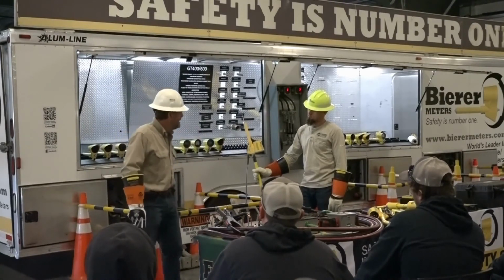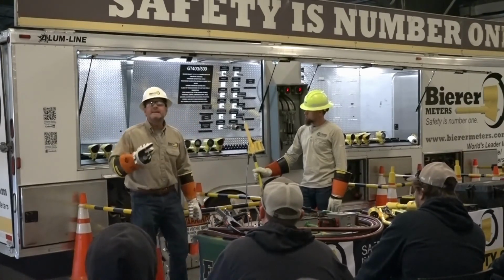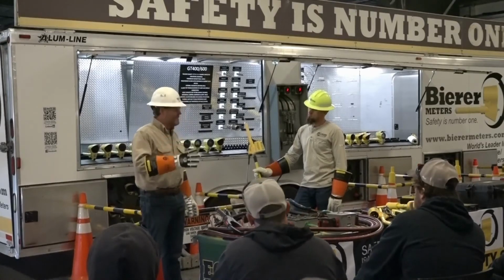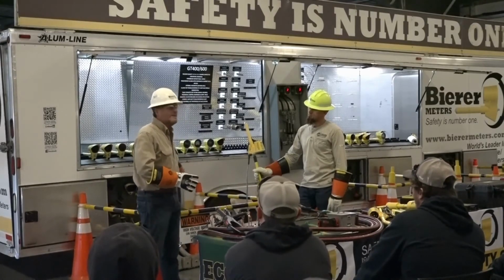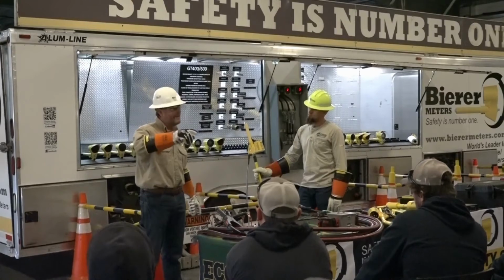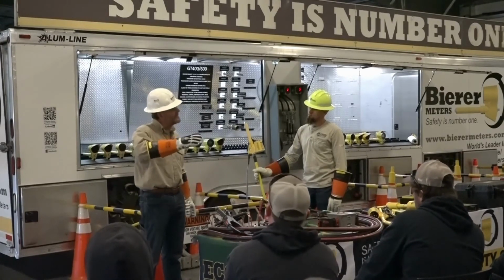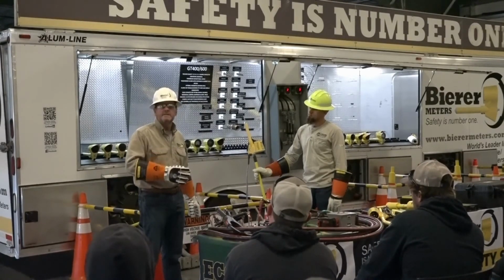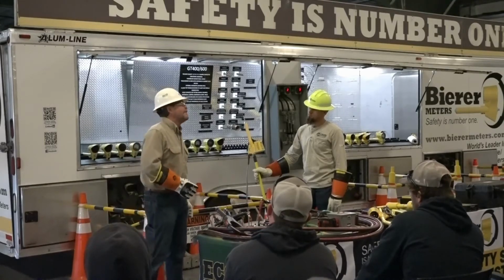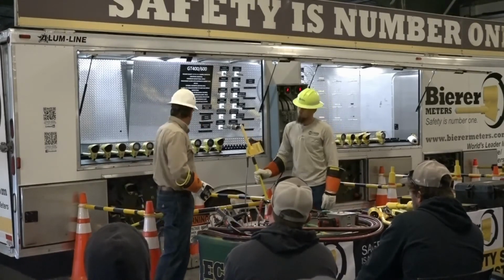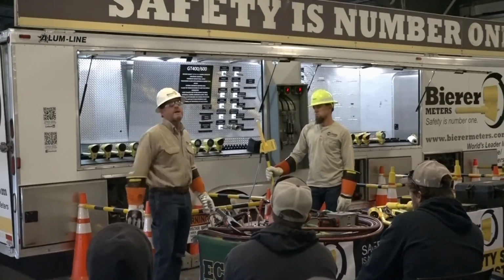He keeps quiet. If he sees about 90 volts, the difference of the two, then he knows we're in phase. You take the difference, subtract it, and if you get close to 0, you're in phase. If you're out of phase, you'll see a multiplier of those voltages close to 600.